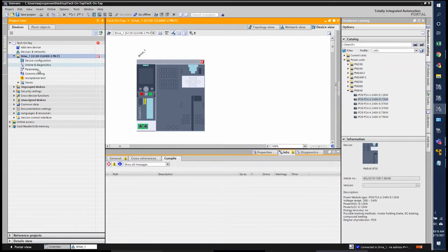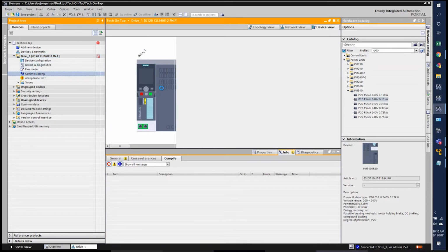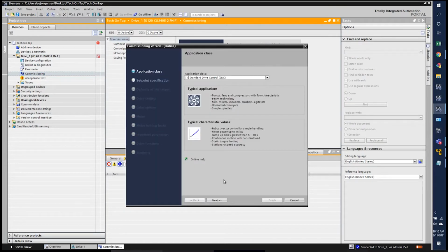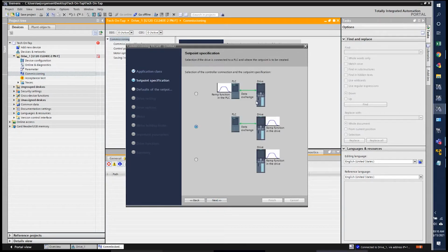All right. Now we need to go through the basic commissioning here. So we're going to step through the commissioning wizard. Our options here are standard drive control or dynamic drive control. For most applications, we're going to select standard here. This selection is where the ramp function is being calculated. We're going to let the drive calculate it and just have the PLC send it speeds and directions and whatnot.